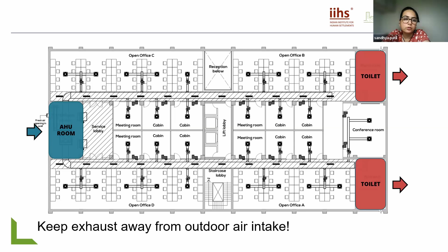Tall buildings nowadays have tended to move the toilets to the core, and this is an issue because it seems spatially more elegant and more efficient, but it's not effective at all when it comes to extraction. When you look at tall buildings, it's very difficult to make sure all the floors are extracted equally, if you have the extraction fan on top. So one of the most important challenges I see is the location of equipment.